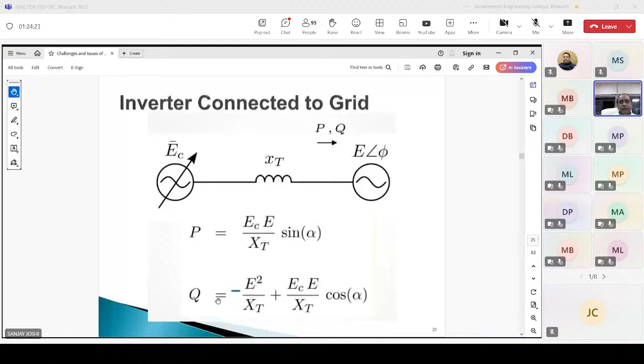And we already have seen that the controllable parameters of VSC are M and alpha. So at the power electronic level, the firing level, we can control M and alpha. So M and alpha are controllable by varying the firing of the devices. So P and Q can be controlled by controlling M and alpha, that is, by controlling the firing.